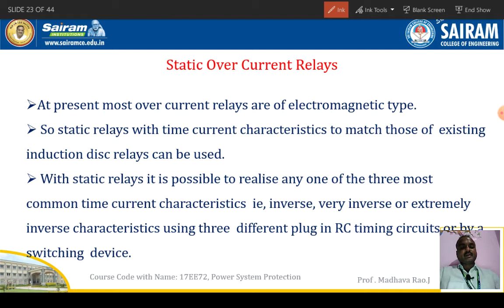Whenever current is more, time will be less. That is called inverse time. Once current increases, the operating time of the relay decreases; once the operating time increases, the operating current is less. So time and current are inversely proportional. The operation of these static overcurrent relays is based on this inverse proportionality of time and current, and that is why we call them inverse, very inverse, and extremely inverse time current characteristics. So this is about static overcurrent relays.